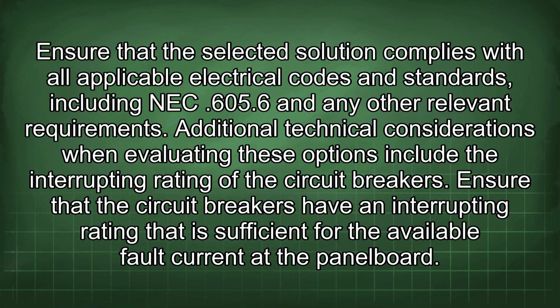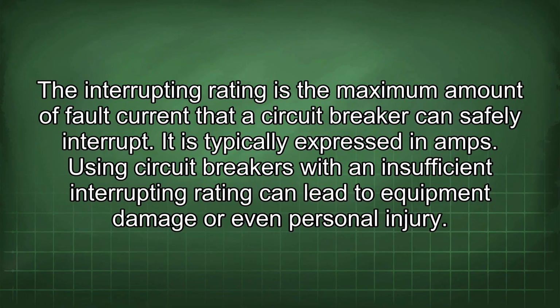Additional technical considerations when evaluating these options include the interrupting rating of the circuit breakers. Ensure that the circuit breakers have an interrupting rating that is sufficient for the available fault current at the panel board. The interrupting rating is the maximum amount of fault current that a circuit breaker can safely interrupt. It is typically expressed in amps. Using circuit breakers with an insufficient interrupting rating can lead to equipment damage or even personal injury.